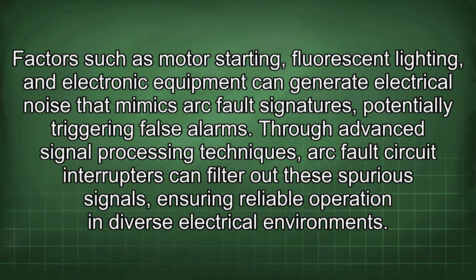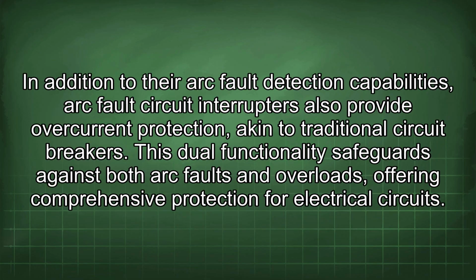Factors such as motor starting, fluorescent lighting, and electronic equipment can generate electrical noise that mimics arc fault signatures, potentially triggering false alarms. Through advanced signal processing techniques, arc fault circuit interrupters can filter out these spurious signals, ensuring reliable operation in diverse electrical environments. In addition to their arc fault detection capabilities, arc fault circuit interrupters also provide overcurrent protection akin to traditional circuit breakers. This dual functionality safeguards against both arc faults and overloads, offering comprehensive protection for electrical circuits.